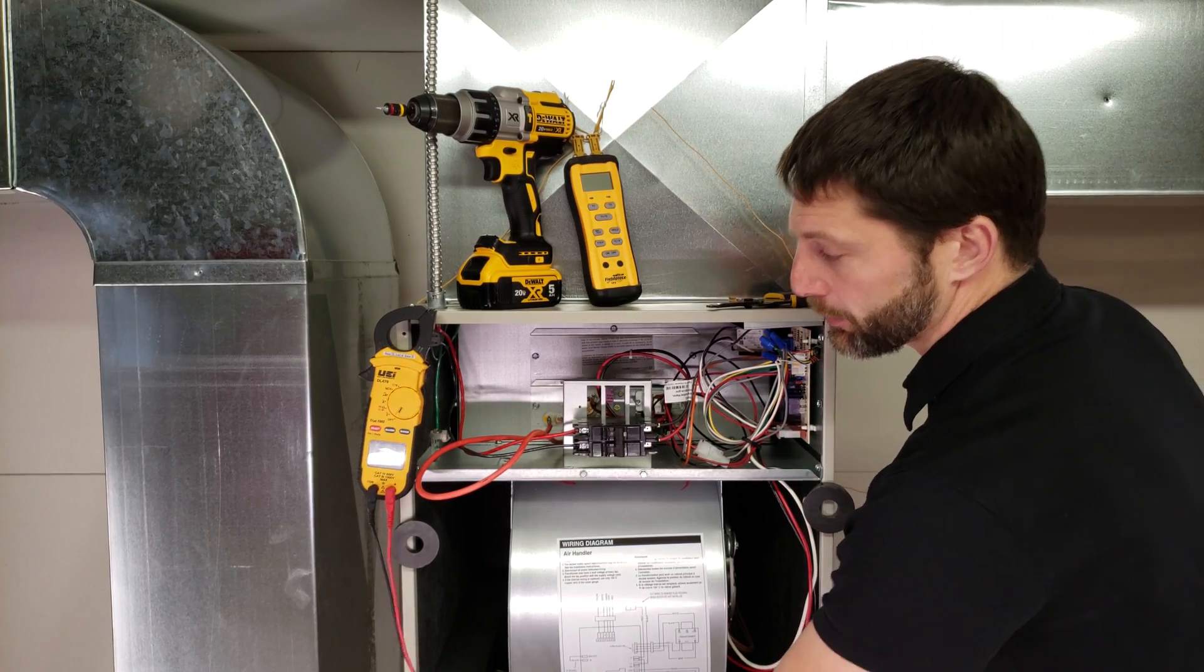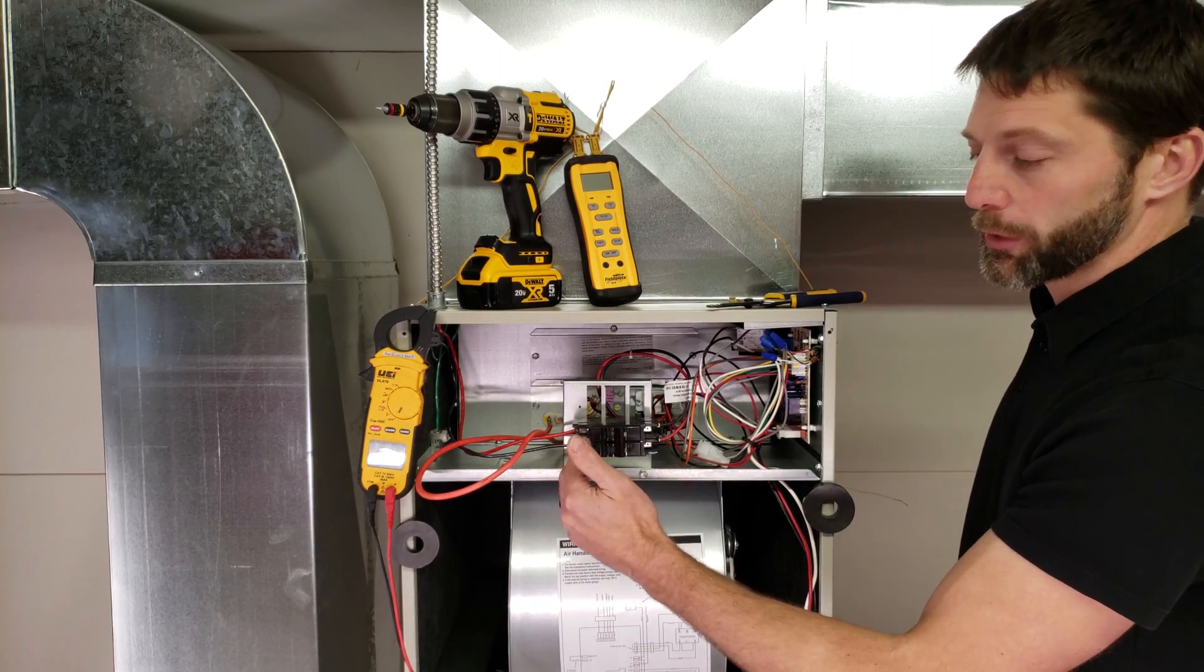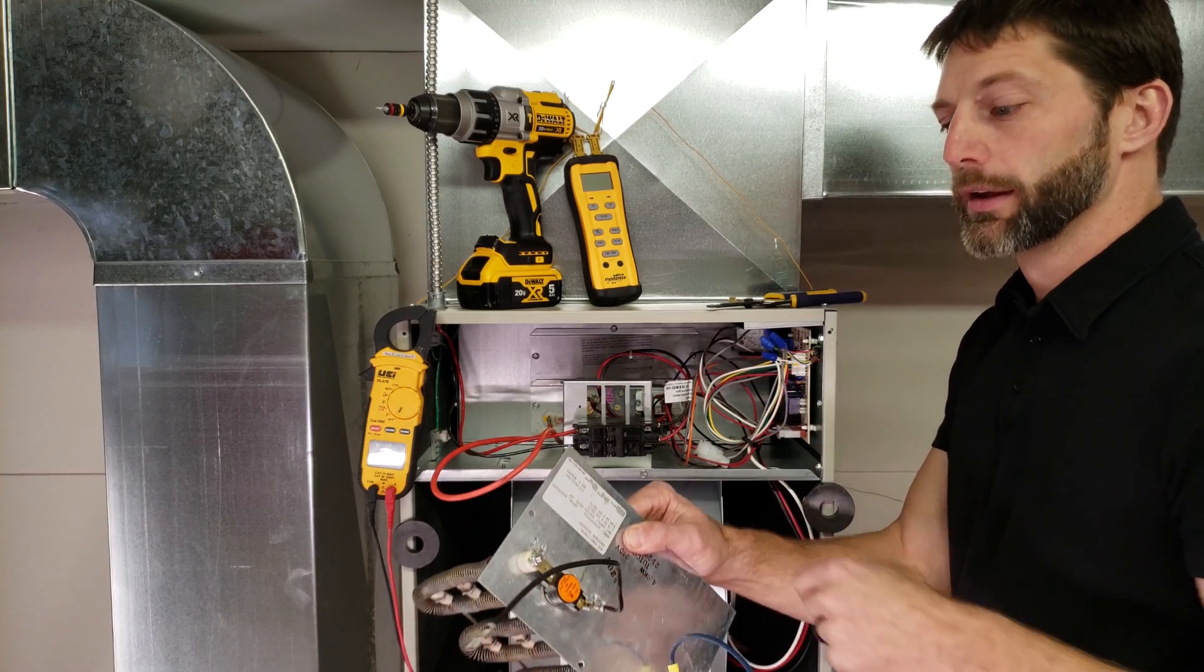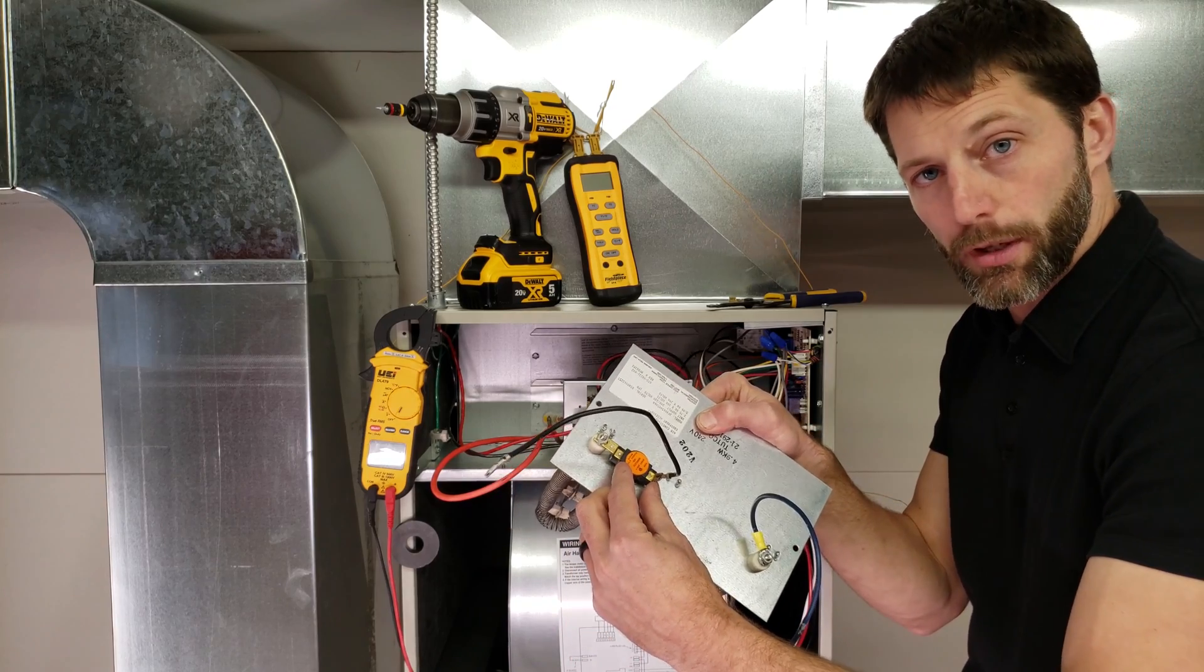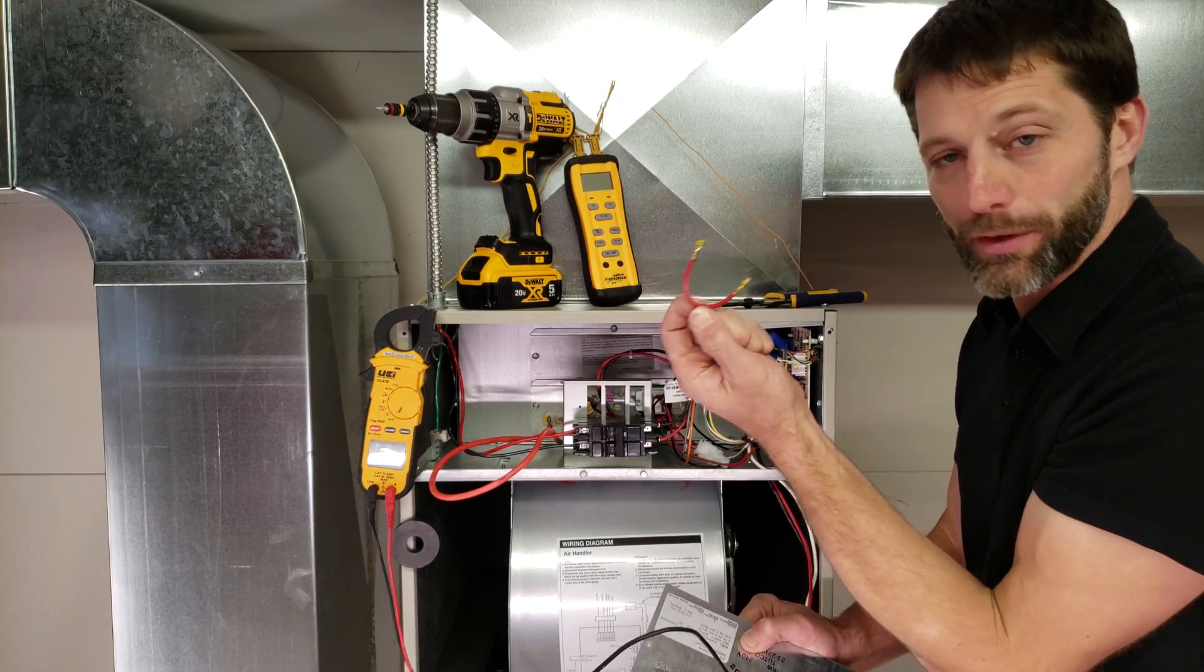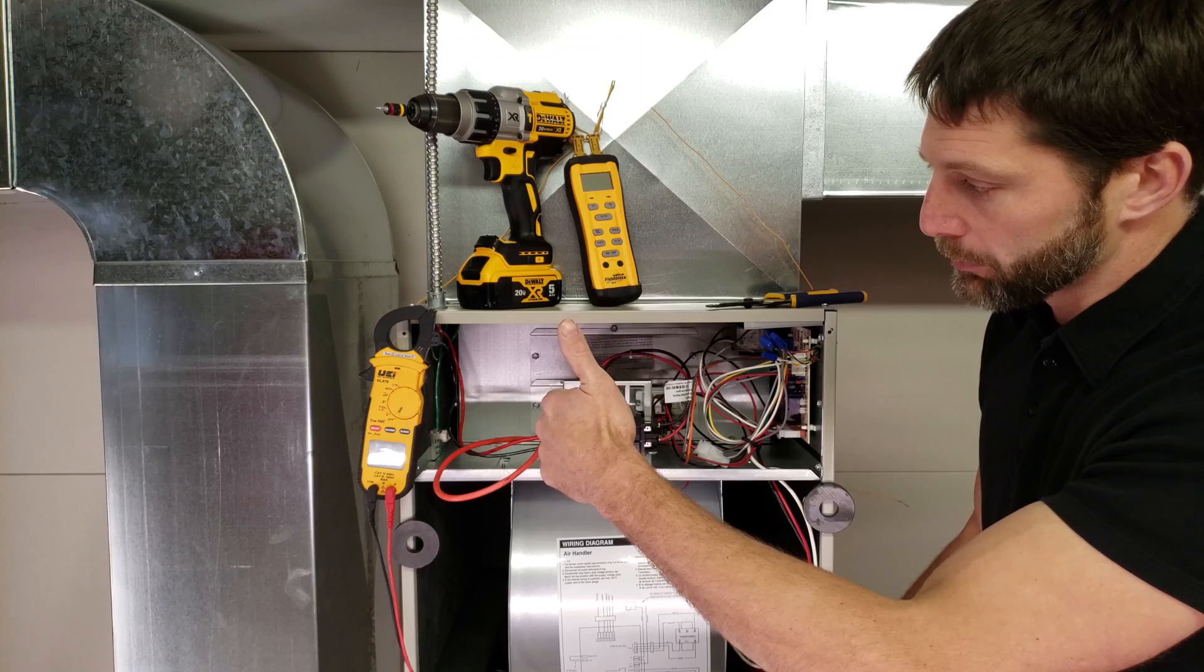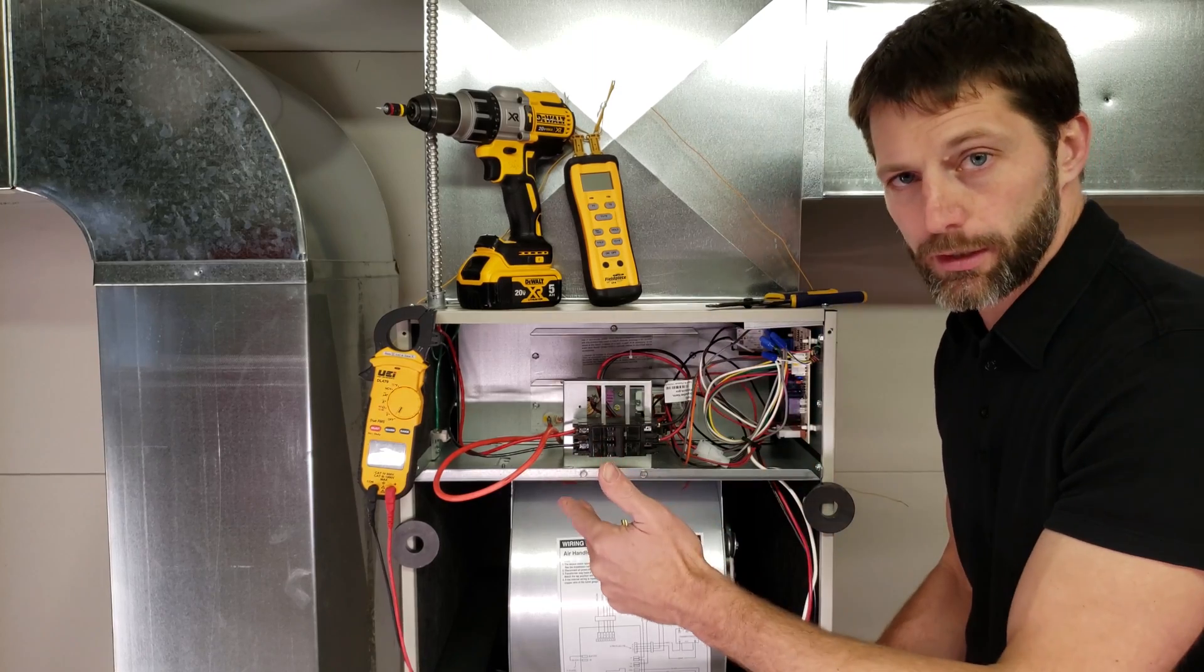Another thing is, in order for you guys to be able to see the amperage, I'm using a large wire, and so you know the power is off, and I did check it with my multimeter to verify that it's off, but I'm using a large wire right here, and what I'm doing is I'm coming off of the electric strip heater. It's actually over here in there, but on the strip heater that's in the inside of here, there's a wire that comes from here, and it goes to the temperature limit, and that's the wire that I'm extending out because the wire that was in there was very small. So I'm just extending it out so I can have my multimeter outside of the electrical cabinet so that you can see it. You don't have to do that in the field. You can just stick your multimeter in there as long as you can still read it. You get that all set up before you even turn the system on, just for safety, and you don't remove it until after you shut the system back off again.